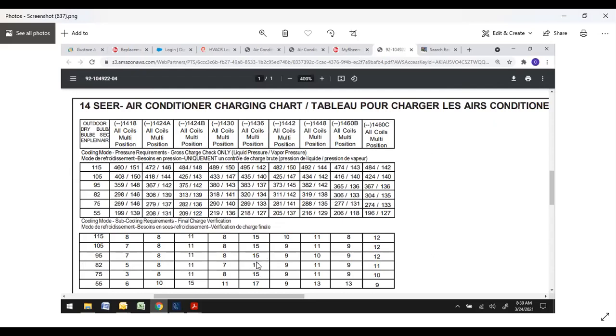That's what you're required. Don't go over the 15. If you need to undershoot that a little bit, do like a 13 to 15, and you'll be fine. But don't overshoot it too much, or you may end up with a high pressure issue. So it's that easy. So if you're on a 95-degree day, come over here. Same thing. Gross pressures of 383, 137. You're in the ballpark.